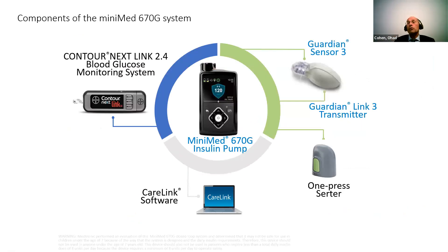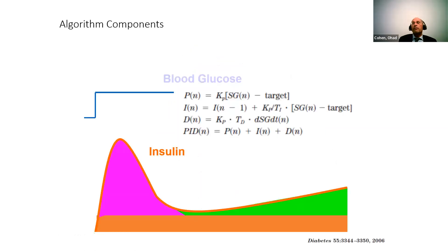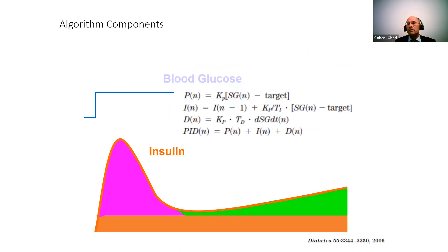We want to also optimize the basal rate to accommodate different demands and reduce hyperglycemia. So the first automated insulin delivery system — the 670G — automated the basal rate. What does automating the basal rate mean? It means there is no fixed basal rate assumption. Every five minutes, the amount of basal insulin is calculated and delivered in a small dose. It's a different concept, and it was very difficult to persuade regulators that this could work.